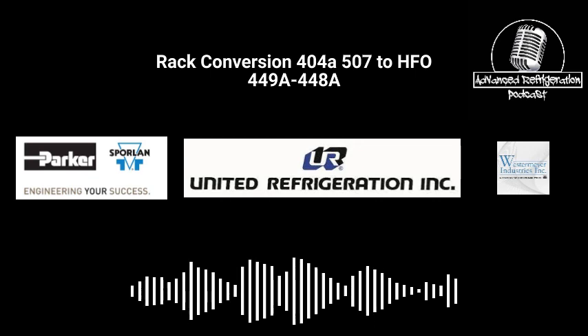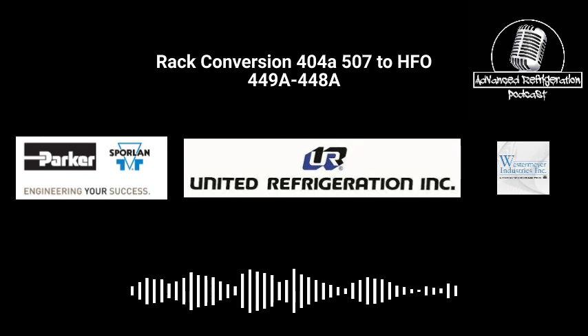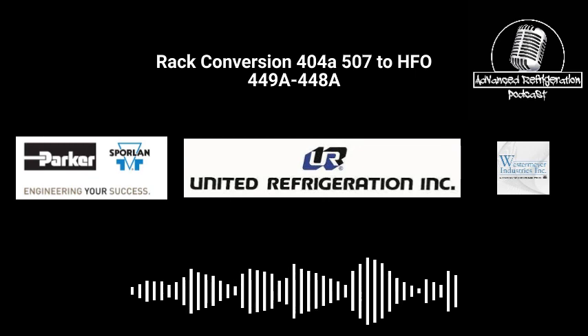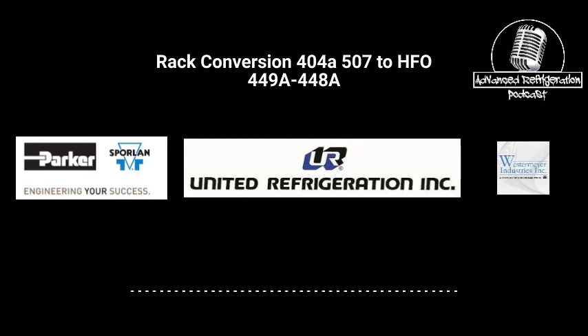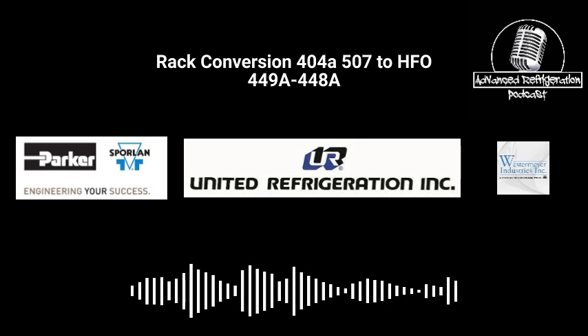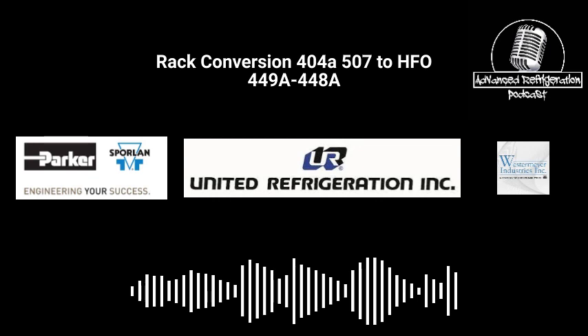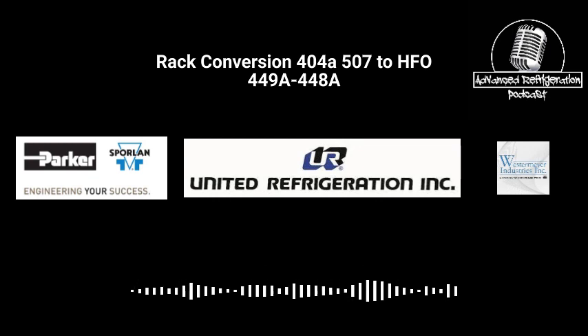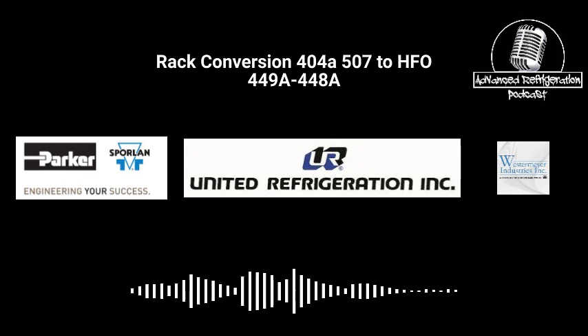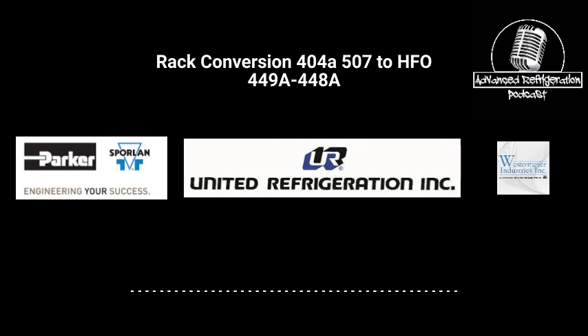100%. I never understood that. I understand a dryer is made for moisture removal, and also filtering, but why do you put a filter before a filter? I don't understand that. Like at the rack? No, I'm talking about why do you put a filter dryer before the TXV if the TXV has a strainer?